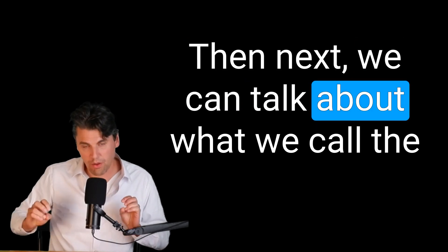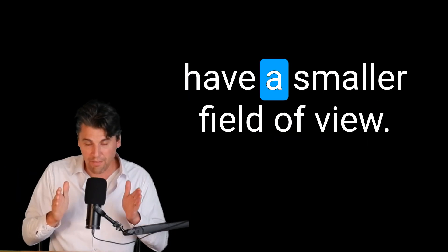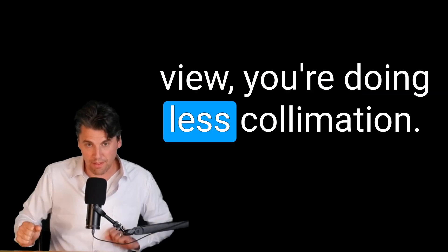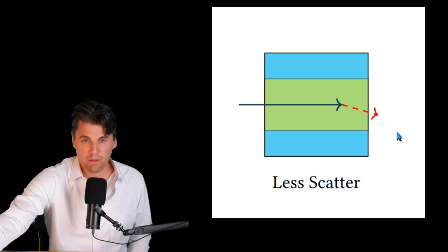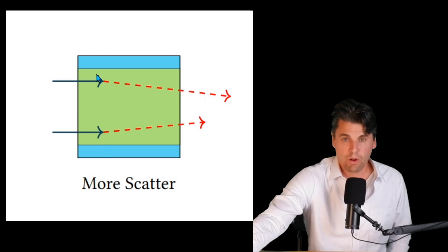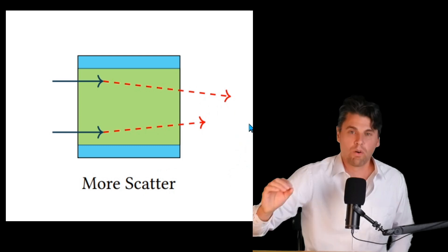Next, we can talk about what we call the field of view or collimation. If you collimate down, you have a smaller field of view. With a wider field of view, you're doing less collimation. As your field of view increases, there's a greater chance for more scatter to interact within the patient and be measured at the image receptor.